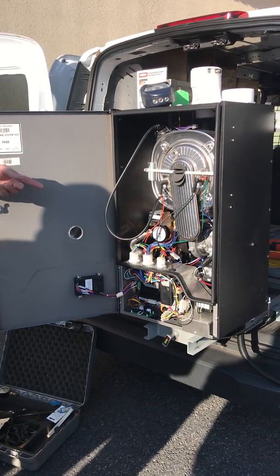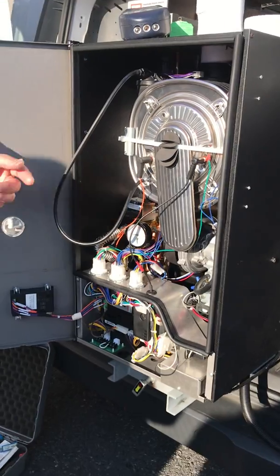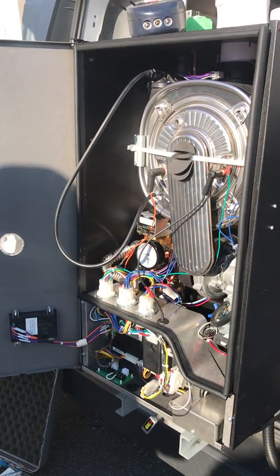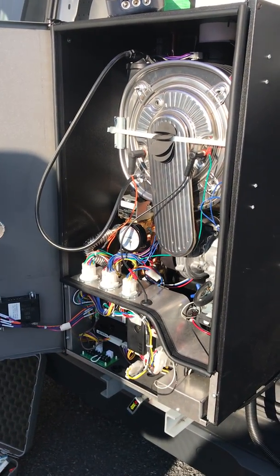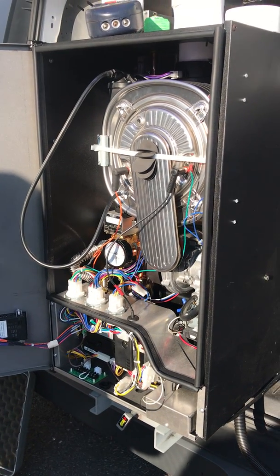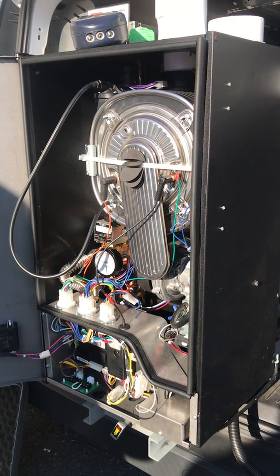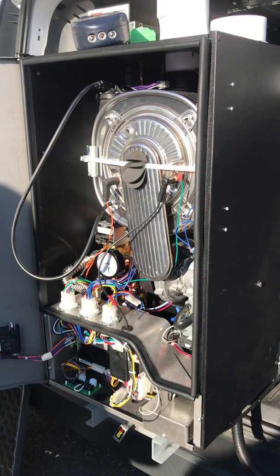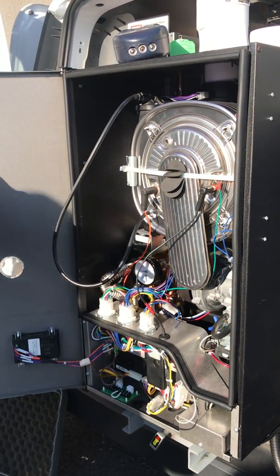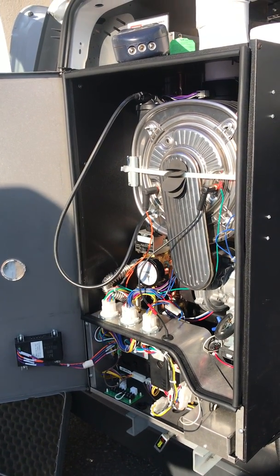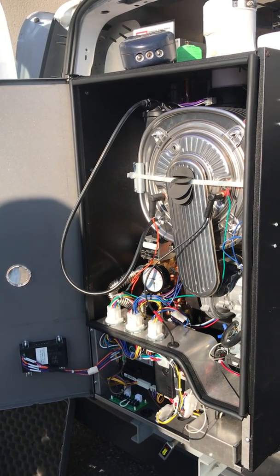And if we don't have the air out of here, or if this pump's not running, it doesn't fire. So it's kind of like a low water cutoff. I'm just letting you know. I don't know that the local township will accept that, but I'm just letting you know. If you have air in this, that unit will not fire. If you don't have flow, it's not going to fire up for you.